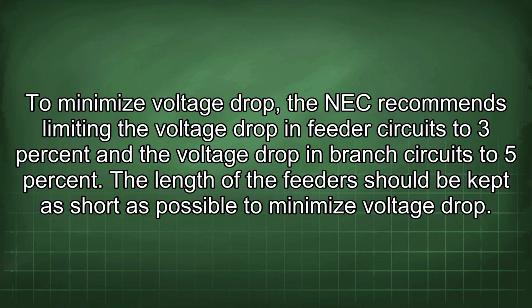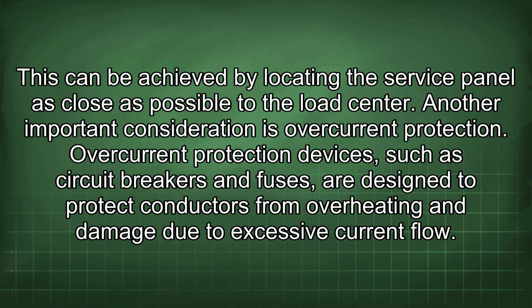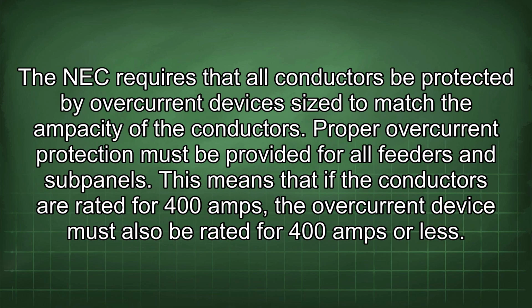The length of the feeder should be kept as short as possible to minimize voltage drop. This can be achieved by locating the service panel as close as possible to the load center. Another important consideration is overcurrent protection. Overcurrent protection devices, such as circuit breakers and fuses, are designed to protect conductors from overheating and damage due to excessive current flow. The NEC requires that all conductors be protected by overcurrent devices sized to match the ampacity of the conductors. Proper overcurrent protection must be provided for all feeders and subpanels.